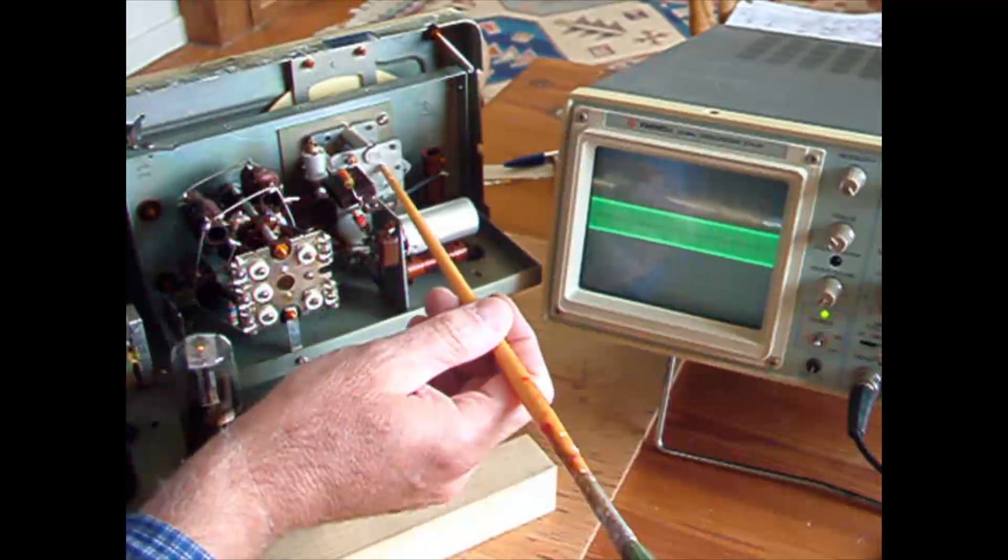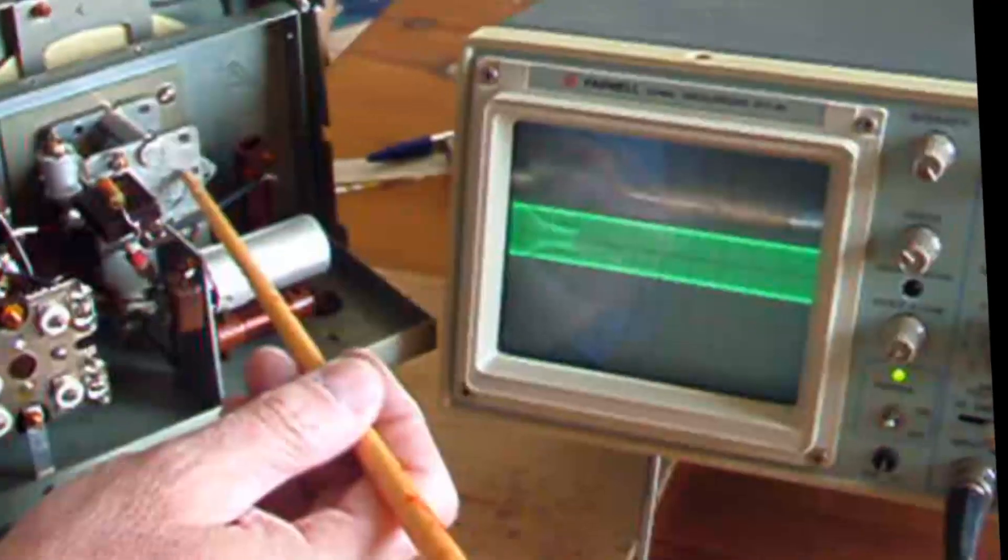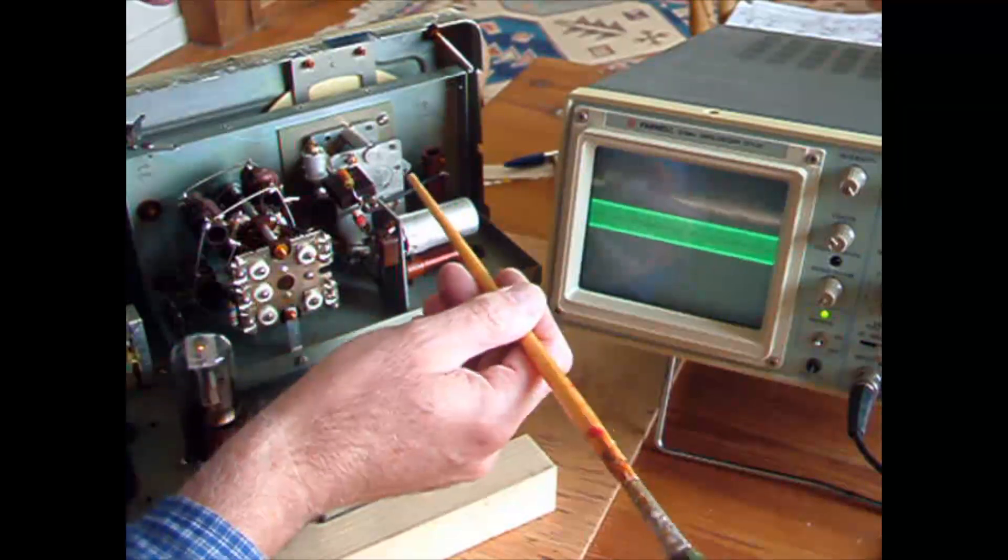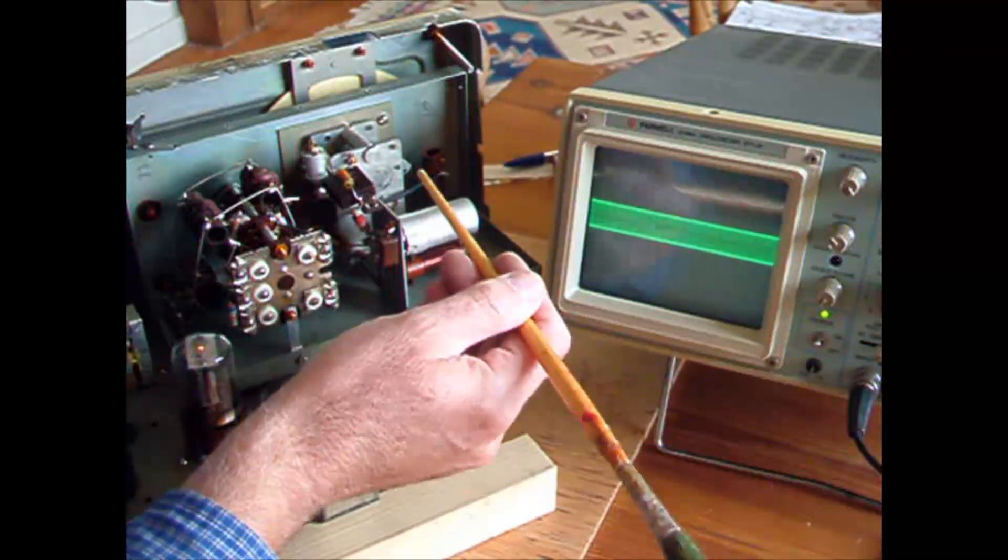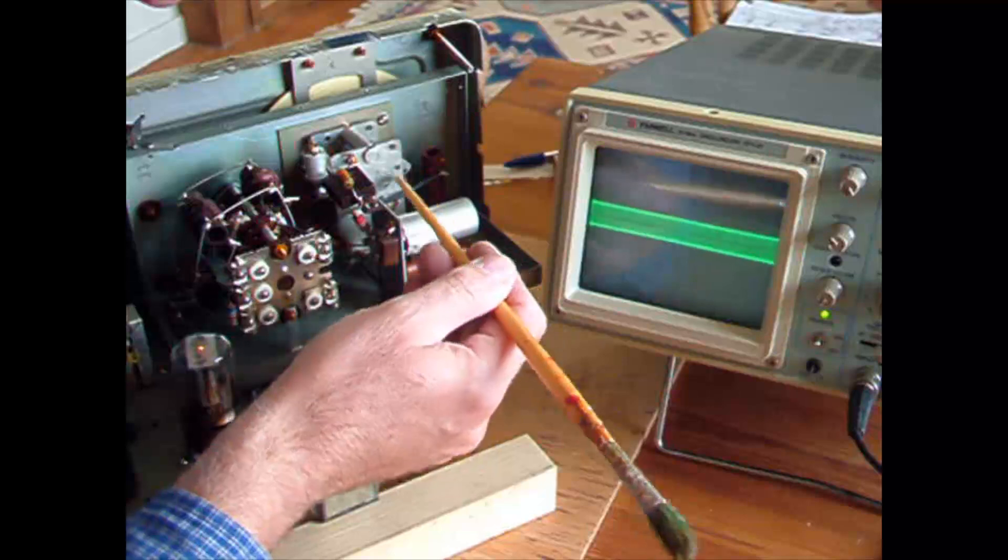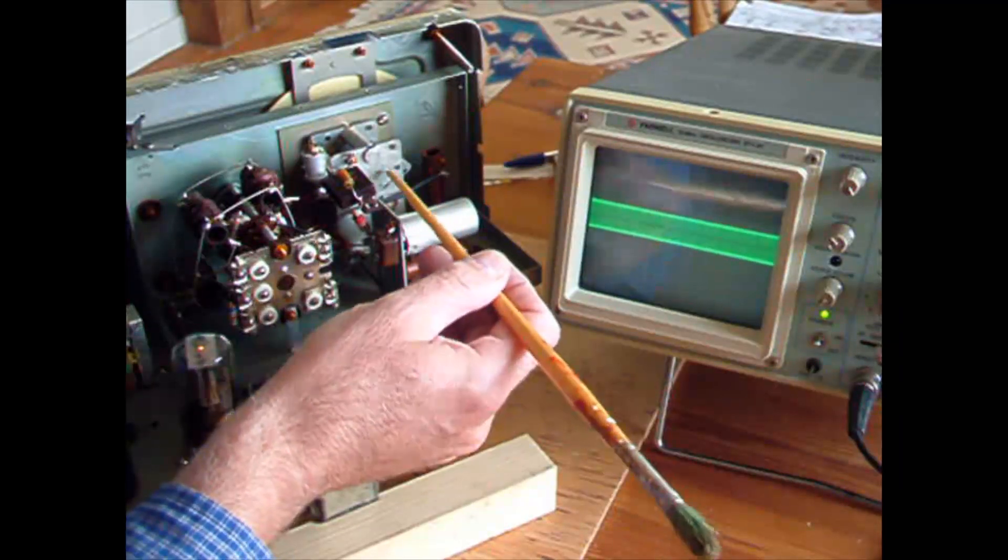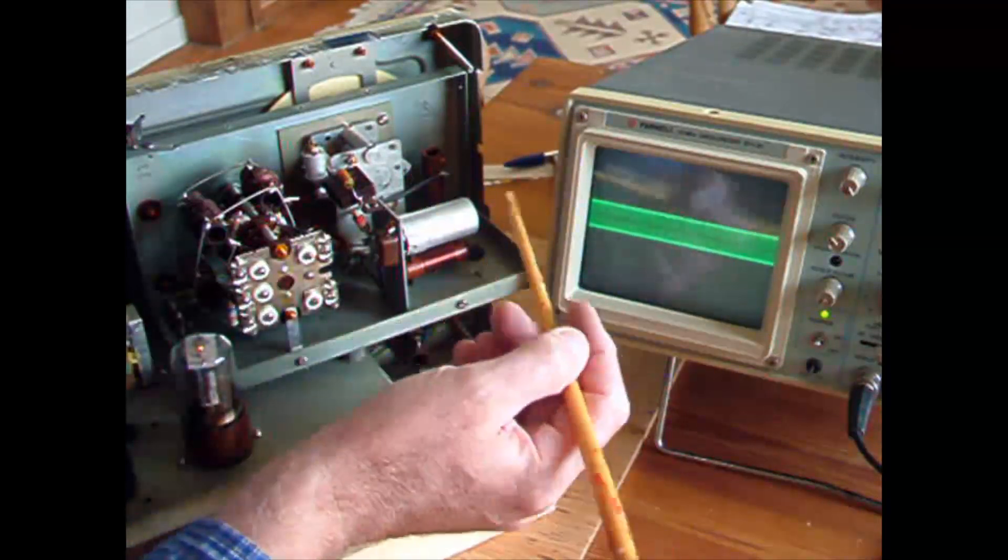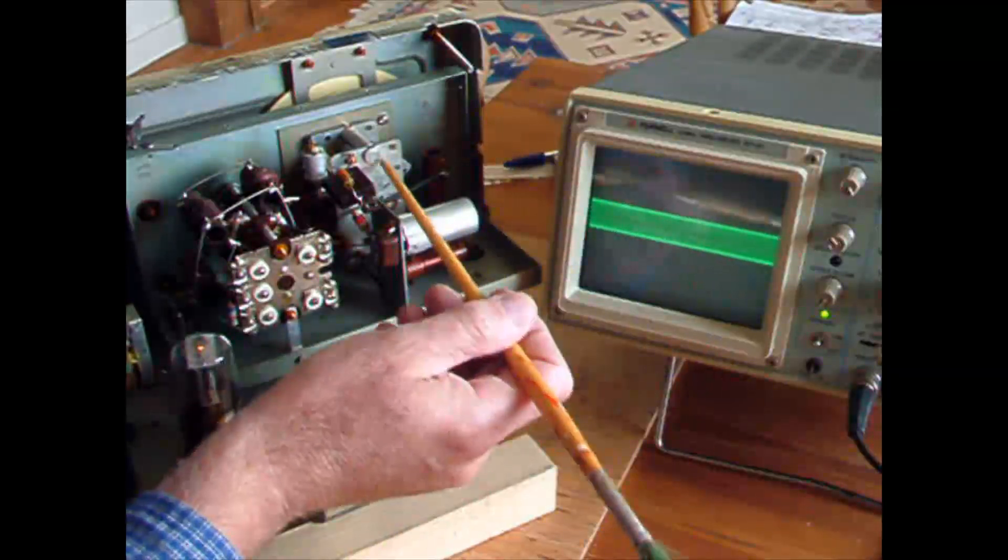And if you look at the trace there, you'll see, I don't know if you can see it actually dip in there. But it's a microphonic fault. And you get the impression if you could shout at it, you could see the modulation there.